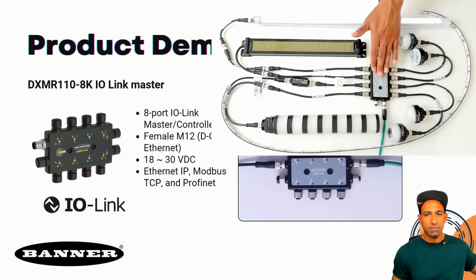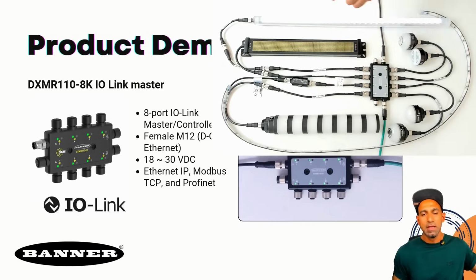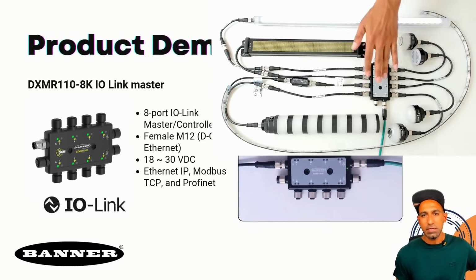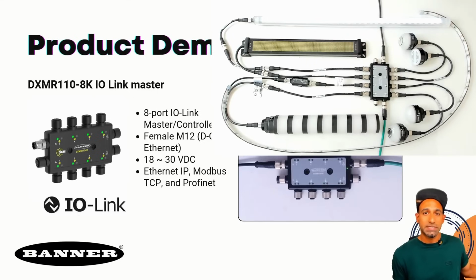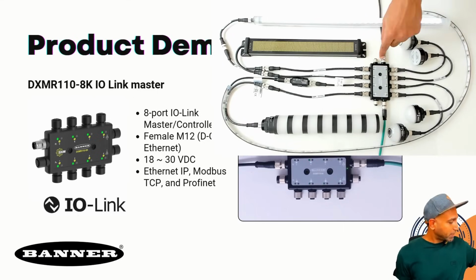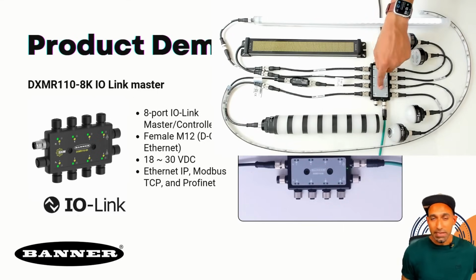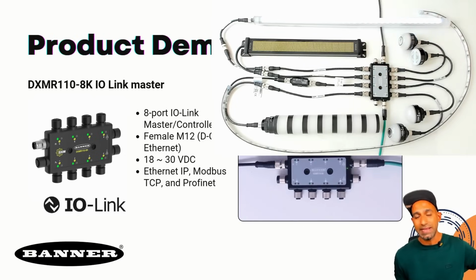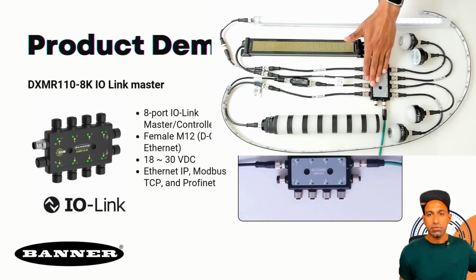Here I have this live demo. This is an IO-Link Master, already connected to several devices from Banner. This is working on nominal 18 to 30 VDC, and it supports EtherNet/IP, PROFINET, and Modbus TCP. So not only can you program this device inside it, you can also connect it to your existing PLC controllers or edge device, and you can send signals to it. You can also read signals from it.